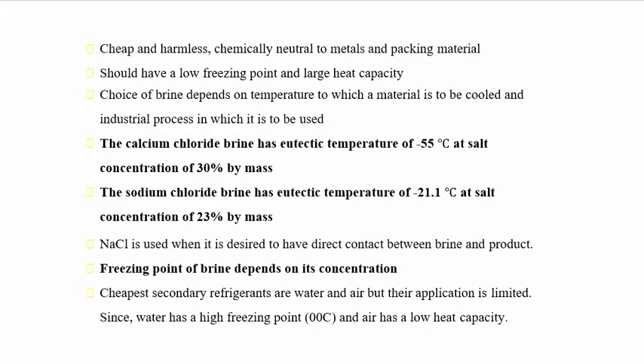The calcium chloride brine has a eutectic temperature of minus 55 degrees Celsius at a salt concentration of 30% by mass. The sodium chloride brine has a eutectic temperature of minus 21.1 degrees Celsius at a salt concentration of 23% by mass. Sodium chloride is used when direct contact between the brine and the product is desired. The freezing point of the brine depends upon its concentration. The cheapest secondary refrigerants are water and air, but their applications are limited — water has a high freezing point of 0 degrees Celsius and air has very low heat capacity.